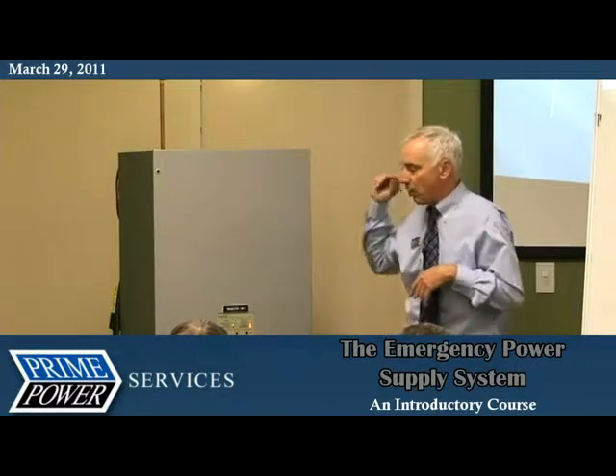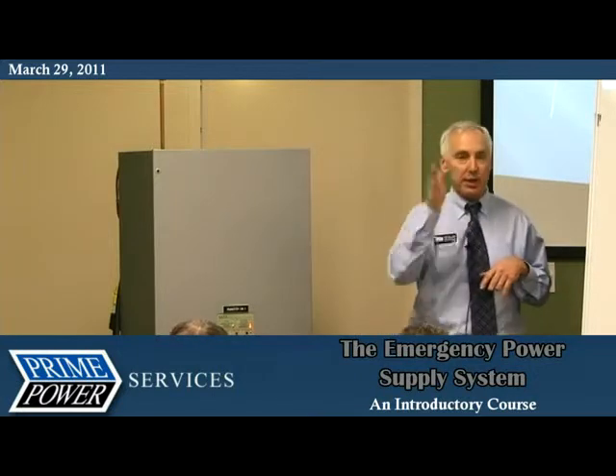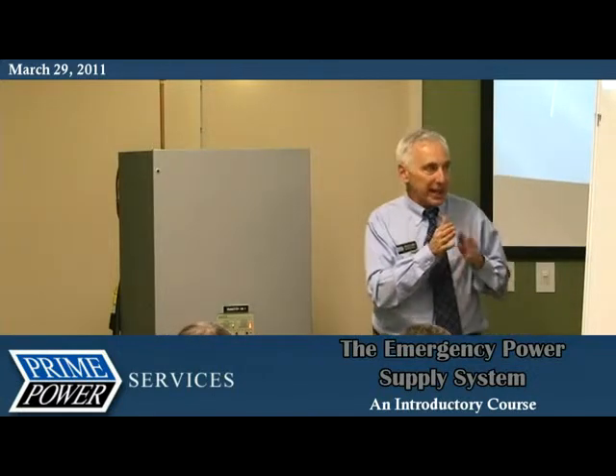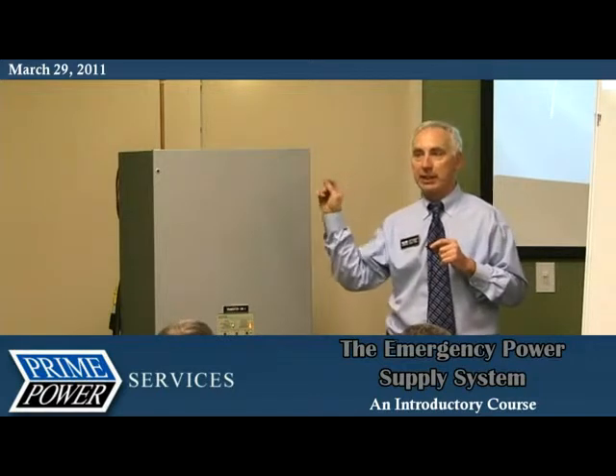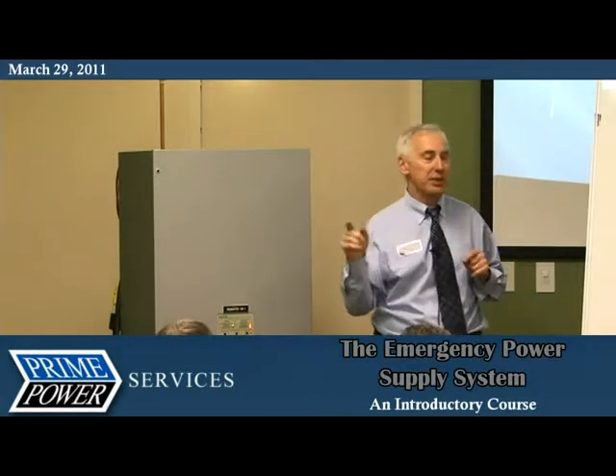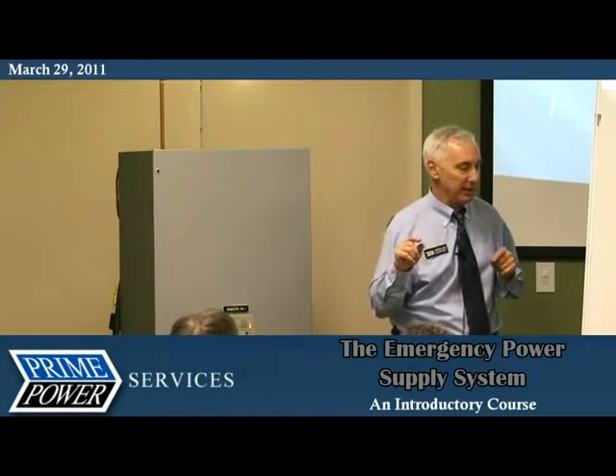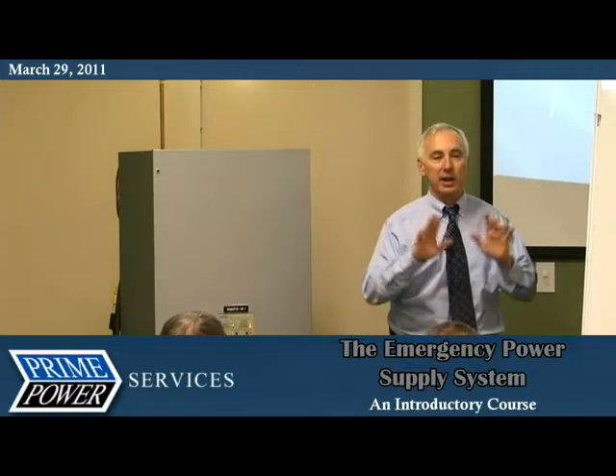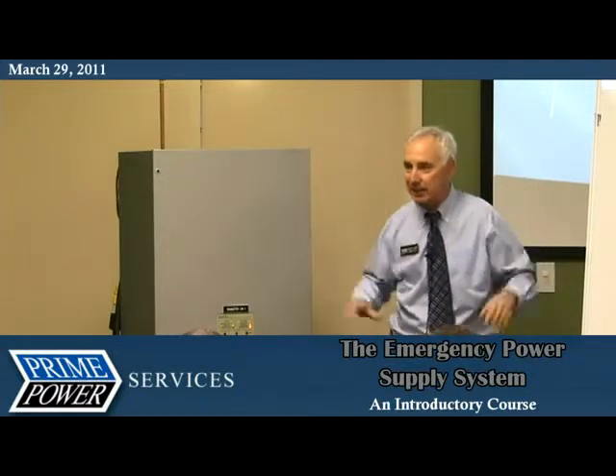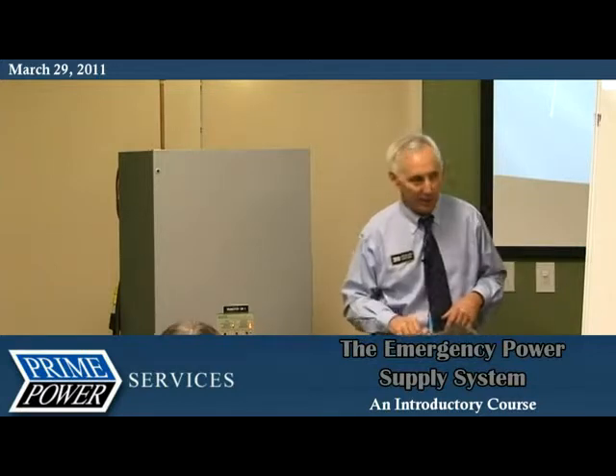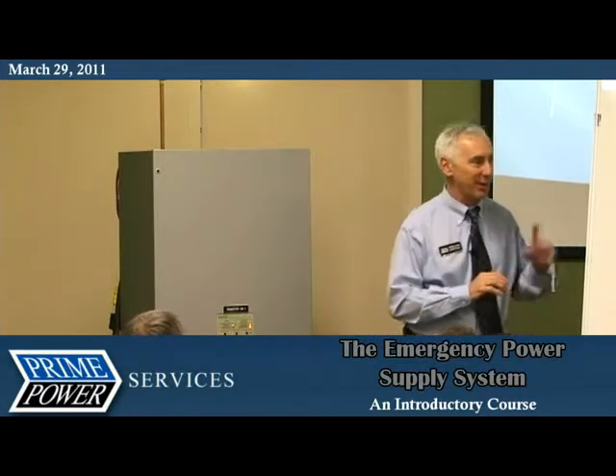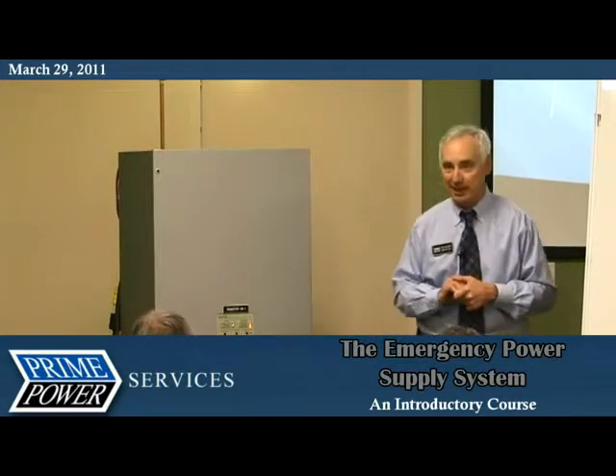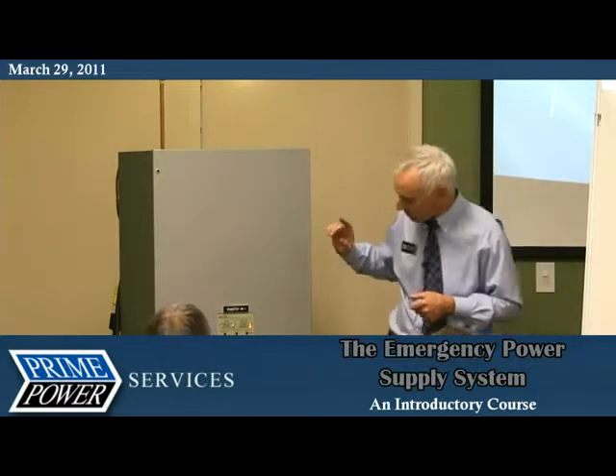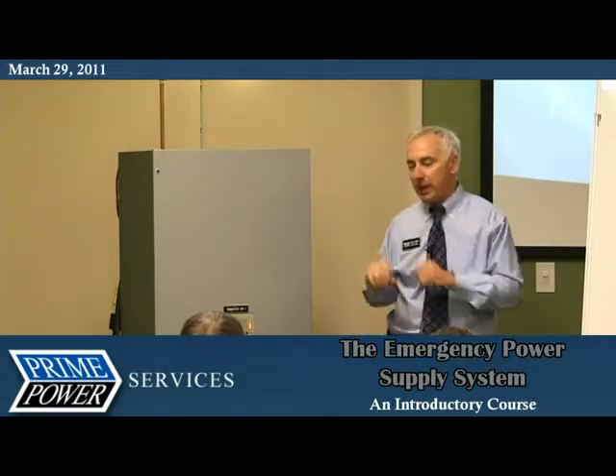Once the generator starts, there's another time delay that comes in, and it allows the generator a stability time. Now we set those at 0, so we're not waiting around. I don't care if it's stable or not. By the time everything else happens, it's stable. One of the best ways to stabilize the generator is to throw a load to it. I'm going to get it stable. I'm not waiting.